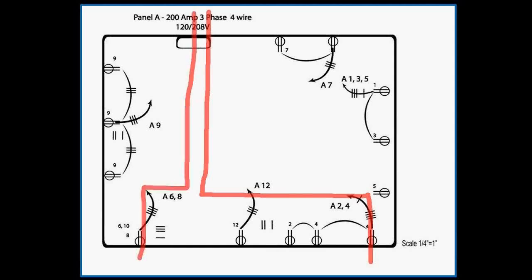This time I'm going to say the total length of run here. I'll roll these both off. I'm going to say that the total length of run for half-inch conduit with four number 12s is 210 feet.